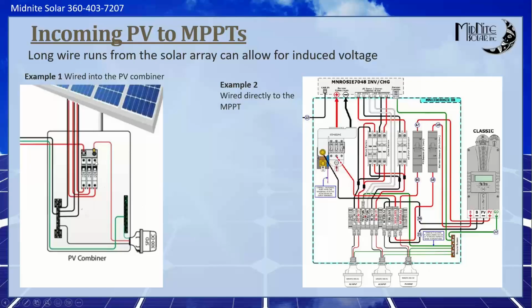Our PV combiner boxes, a lot of the bus bars have a second hole, so you can crimp a ring terminal on the wire and land it on the bus bar. If it's a combiner and you're not using all the strings, you can throw an extra breaker in there. We'll show a picture of that, I think, in a little bit. The Rosie panel, for example, has pickoffs that you install to install your SPDs for AC in and AC out, PV and battery if you need to. Just get that connected as close to the electronics as you can, and keep the wires on the SPD as short as you can. Nice sweeping radiuses, no sharp bends, etc., etc.